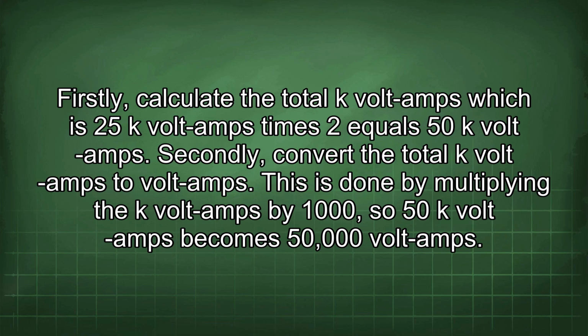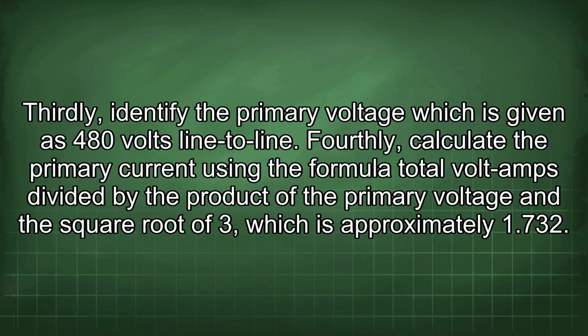Secondly, convert the total kVA to volt amps. This is done by multiplying the kVA by 1000, so 50 kVA becomes 50,000 volt amps. Thirdly, identify the primary voltage, which is given as 480 volts line to line. Fourthly, calculate the primary current using the formula total volt amps divided by the product of the primary voltage and the square root of 3, which is approximately 1.732.